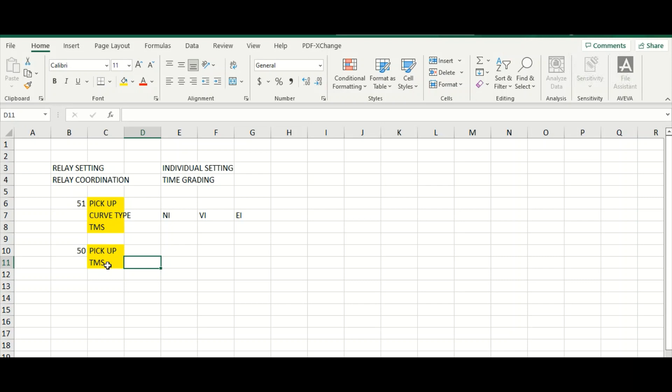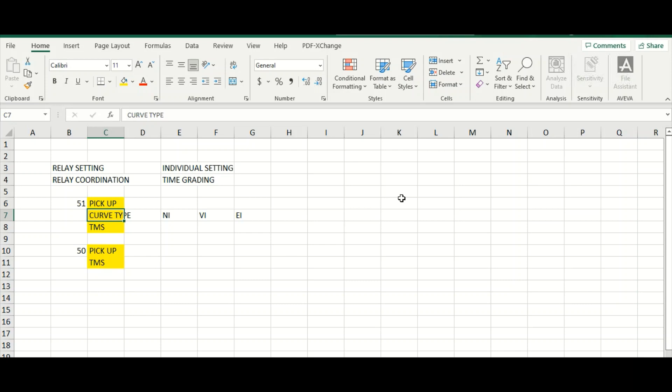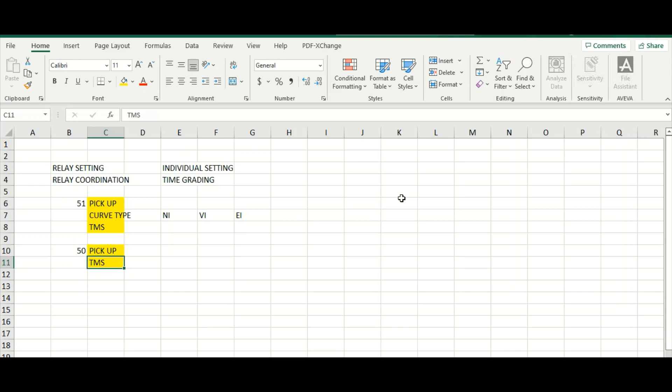Say 100 milliseconds or like this, but not that bigger TMS setting. I will tell you with the help of ETAP software. So once again, for 51 we need to specify the relay pickup current, then curve type, then TMS. These three parameters we need to specify for 51, and for 50 only the pickup and TMS.